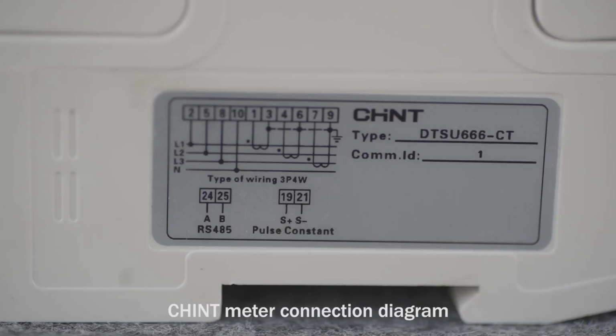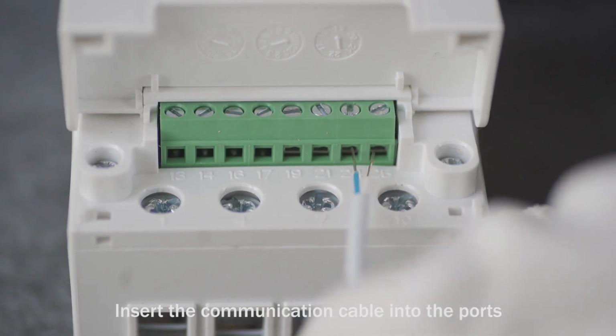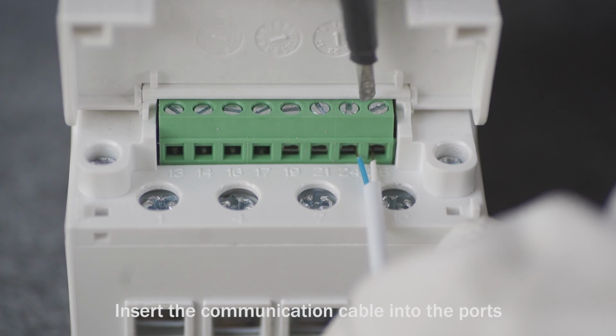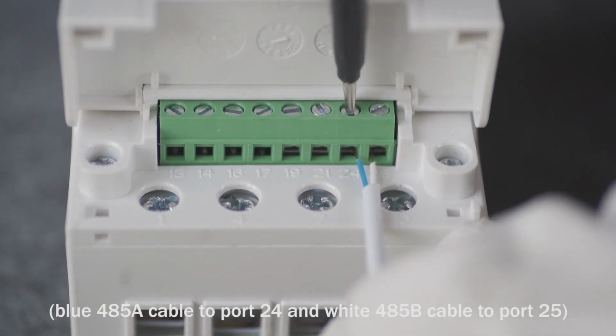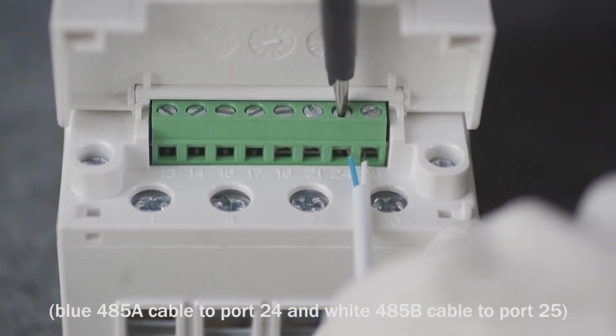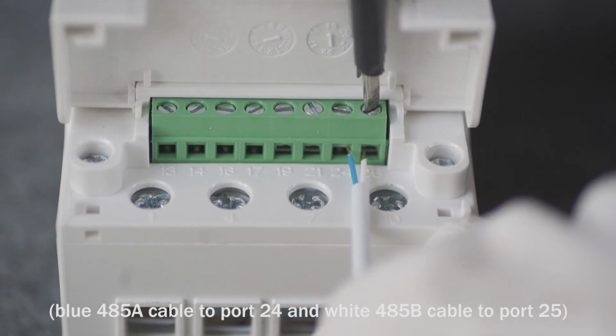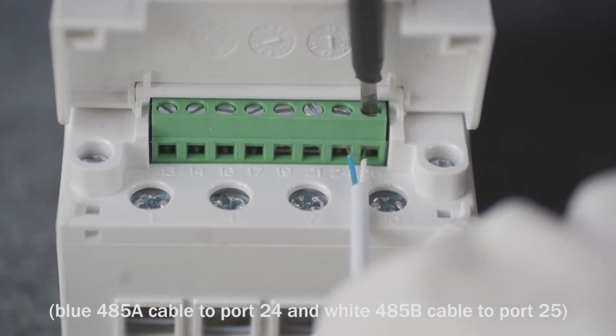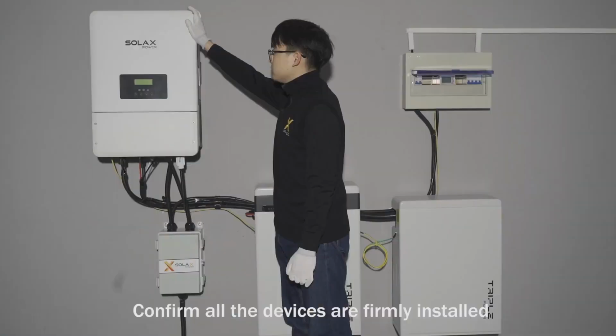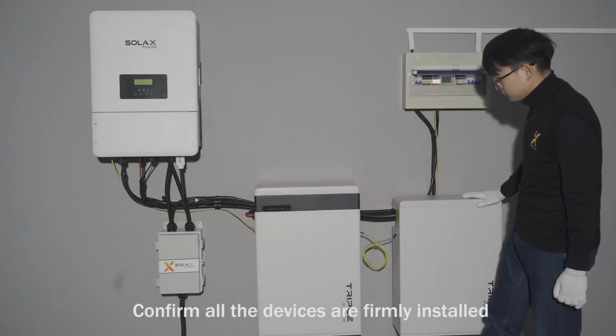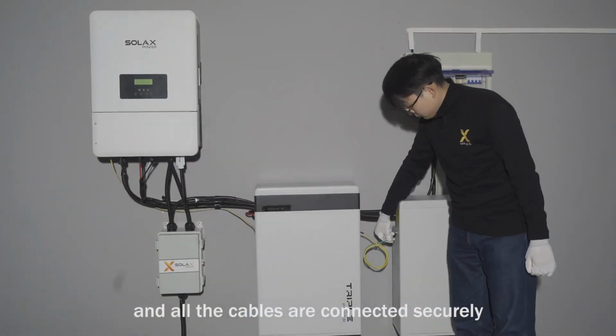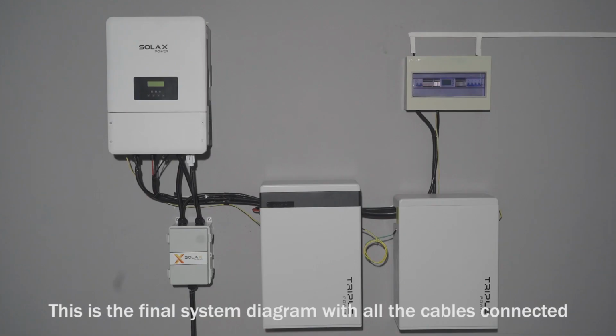CHINT meter connection diagram. Insert the communication cable into the ports. Blue 485A cable to port 24 and white 485B cable to port 25. And tighten the screws. Confirm all the devices are firmly installed and all the cables are connected securely. This is the final system diagram with all the cables connected.